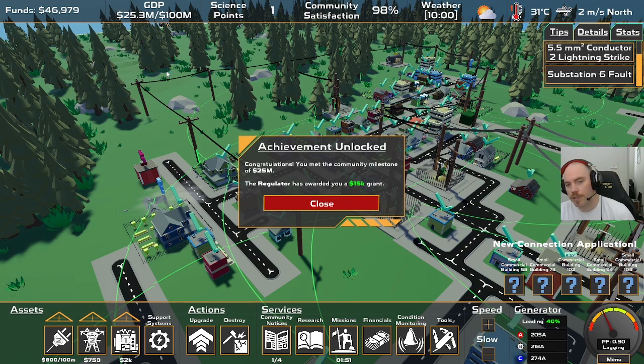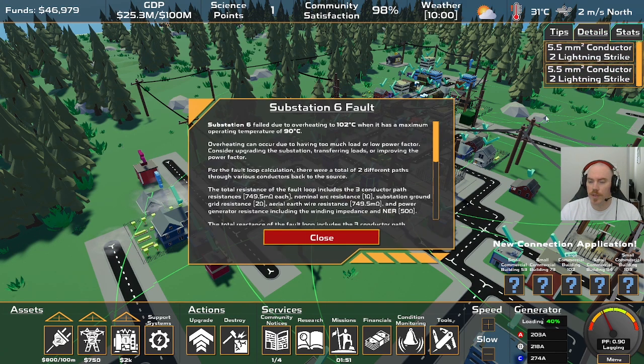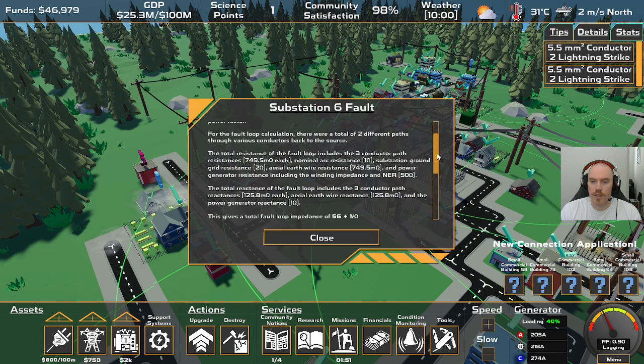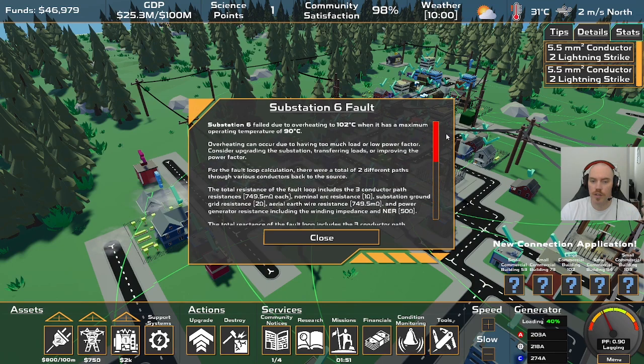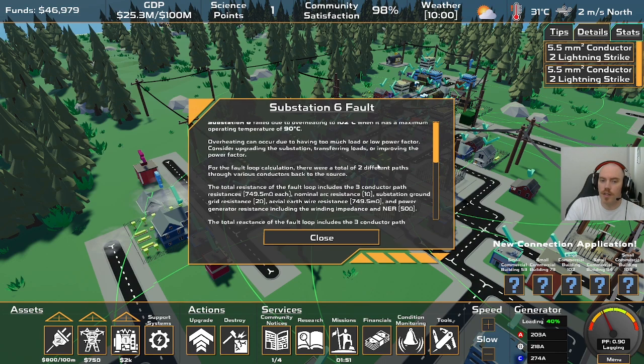It might be an option to expand some of these, but there's a lot of calculations happening to determine these voltages and make it realistic, essentially designing for this substation under these conditions, with this soil resistivity, to work out whether it's a dangerous or safe environment. There's a lot of calculations occurring, and I've tried to display some of them under the details here. For that substation that just overloaded, this is essentially a detailed calculation of what you'd do in a design, working backwards from the earth installation to figure out what voltages and earth fault currents you'd expect. I tried to provide this, and it's something I'll expand on later.